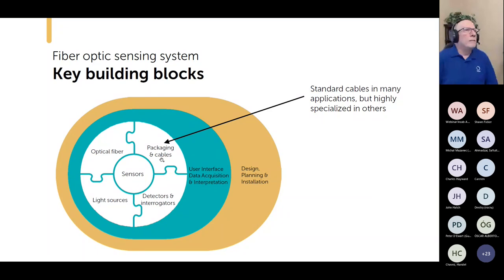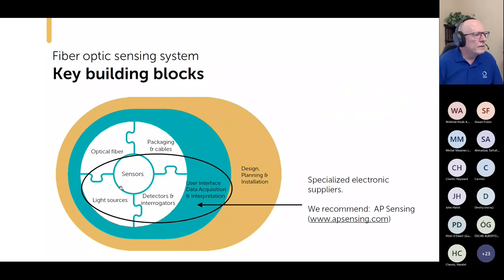I talked about putting in a fiber that senses strain. Well, most aerial cables today, like 99% of them, are loose tube construction. And one of the reasons you use loose tube construction is that you try to protect the fibers from strain. So that means if you want to measure strain in an aerial cable, you have to now put in a fiber that is essentially non-loose tube. But that's readily done. It's not particularly hard to do, but it does make it a little bit special. As I say, for many applications, just cables you're already using can be used. The sensors, the light sources, and the interrogators, there are companies that do that. There are a number of them. AP Sensing is one that we work with. They do these components, and they do it well.